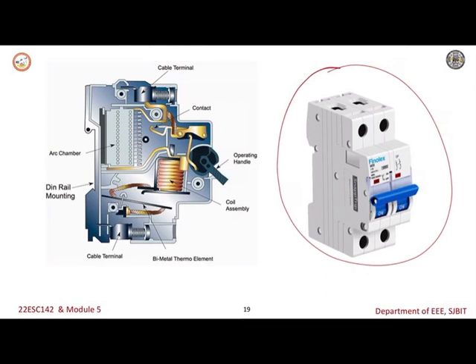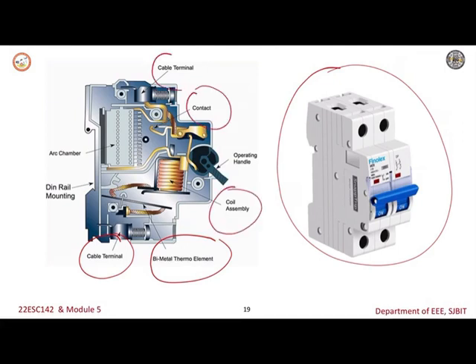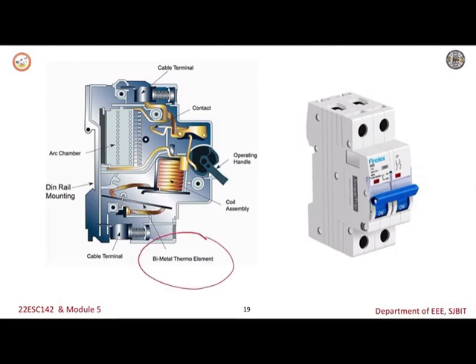So then what is the working principle of this? Here you can observe in the circuit we have a cable terminal, a bimetallic strip, the coil assembly, the contacts, a cable terminal, the arc chamber, and the operating handle. Whenever an overflow of current takes place through the MCB, the bimetallic strip gets heated. So here you can see the bimetallic strip. It gets heated and it deflects by bending. So it will bend and be deflected like this.